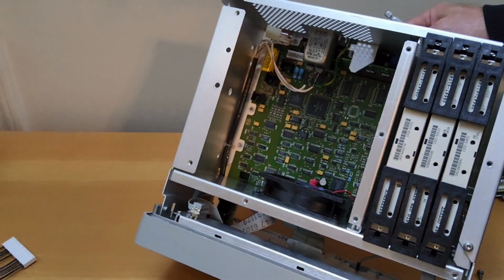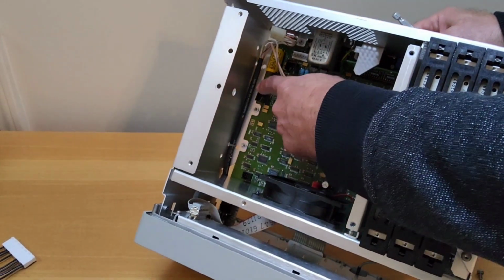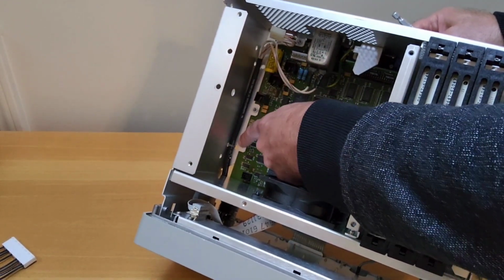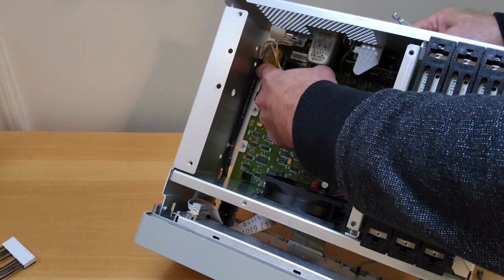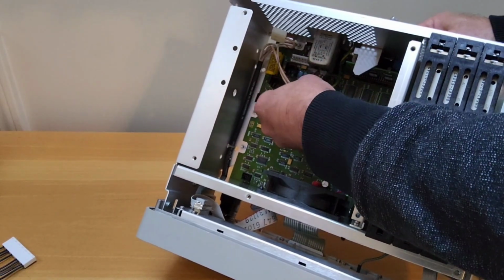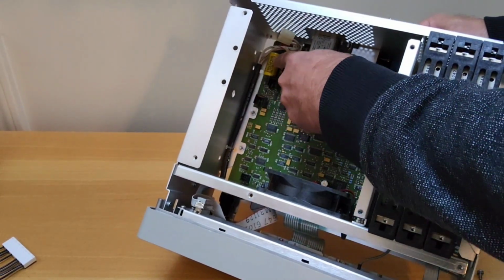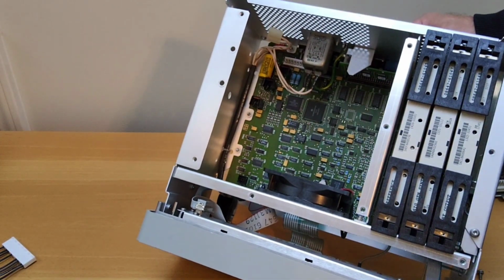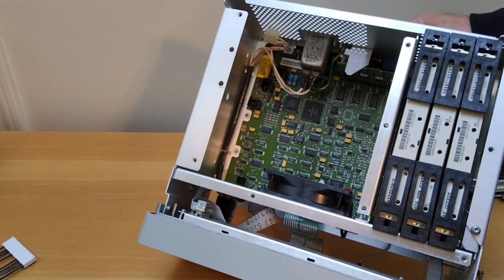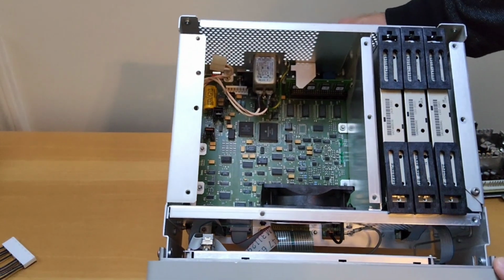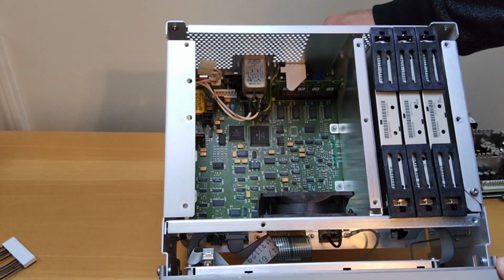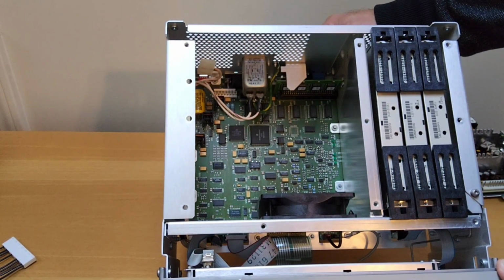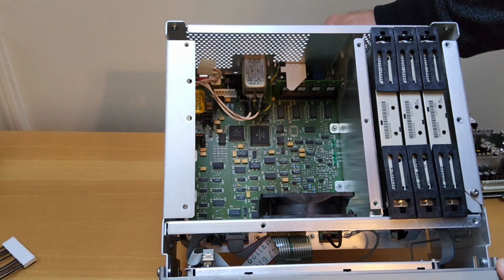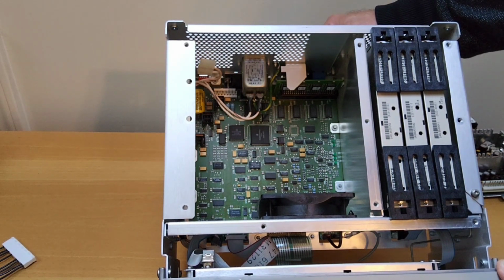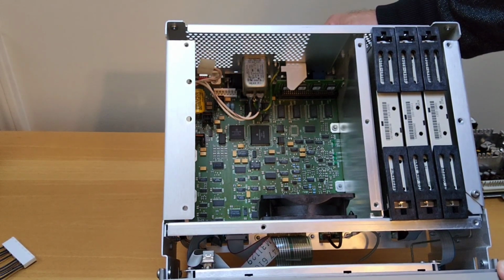And with the power supply removed, I'll show you the main harness from the main switch is actually zip tied on the corners. I had to remove one of the zip ties, which I will later replace. And this is where we see the battery. That's the battery for the settings of the unit when it turns on. This unit does have some calibration data that's stored on ROM, and then on power on supposed to be pulled into RAM to use. So hopefully all that data is still good.